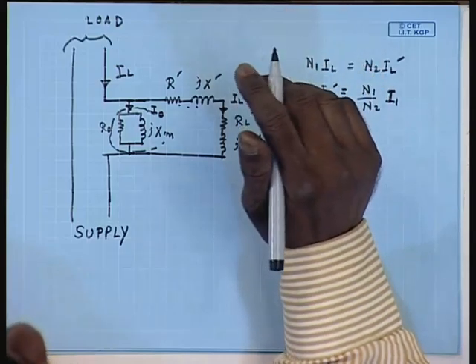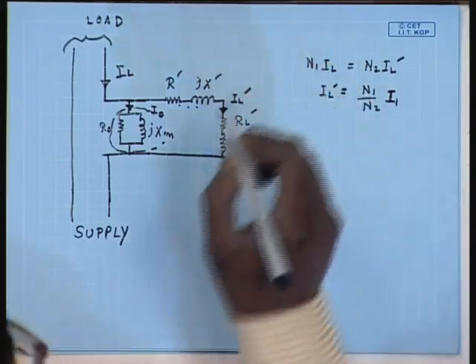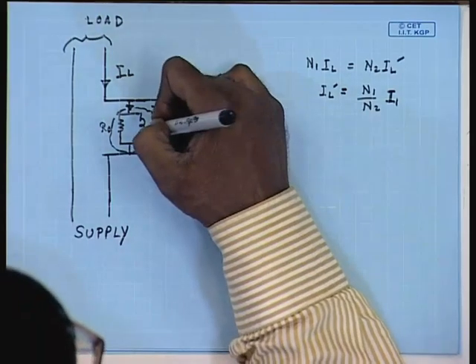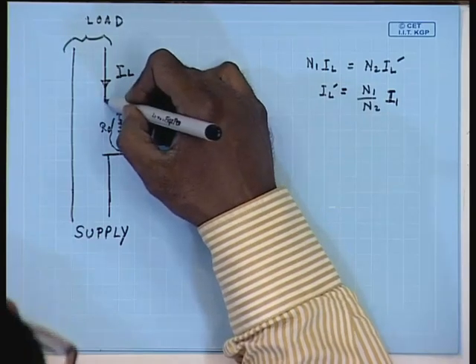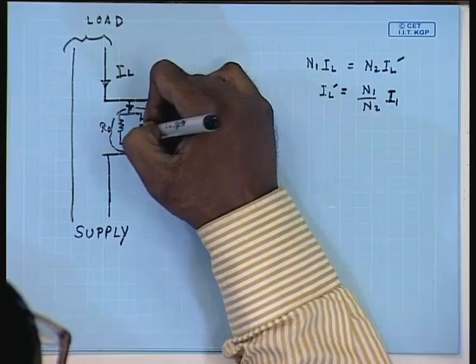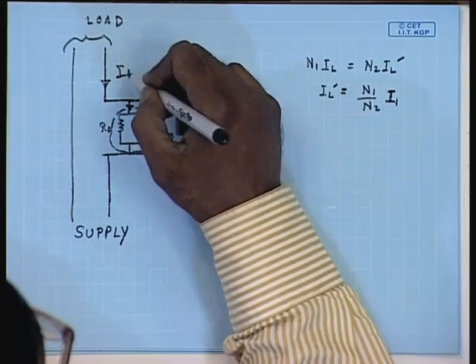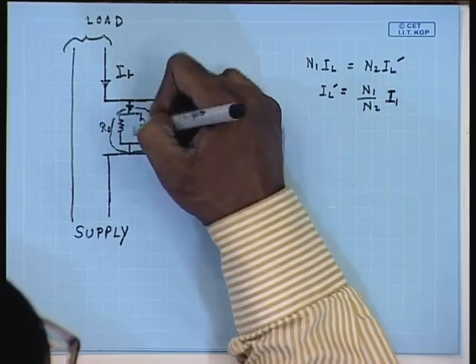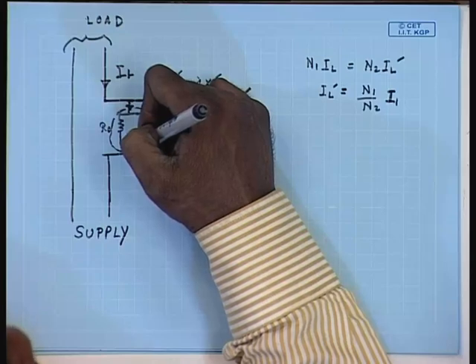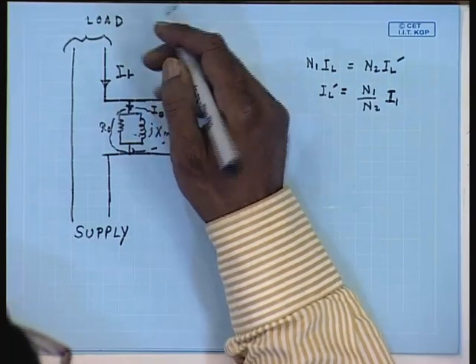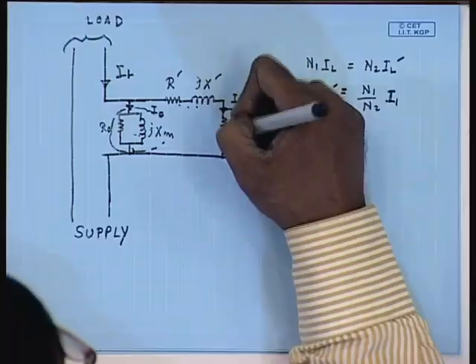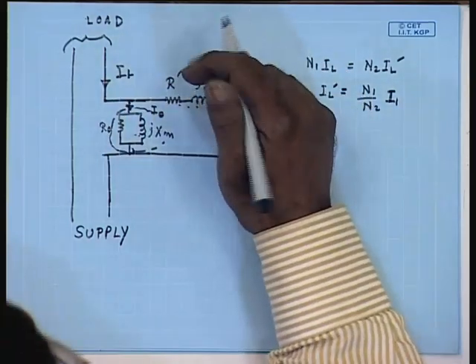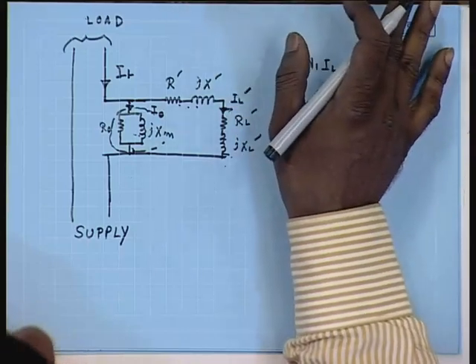However, there is another important point here. It can be seen that even by accident, if the load is open circuited, then a relatively large magnetization branch impedance is put in series with the line, but even then that impedance is small compared to the load. Hence, this impedance does not affect the load current much, but what it does is the voltage drop across the CT increases very much, and along with that the flux density in the CT increases and the CT core saturates. Once it saturates, its properties change, and hence that CT cannot be used any longer. So, care should be taken that when the current is flowing through the primary, the secondary of the CT should not be open circuited even accidentally.